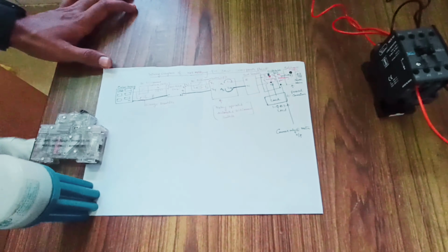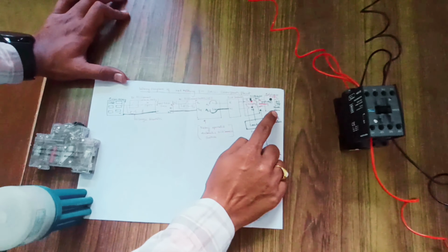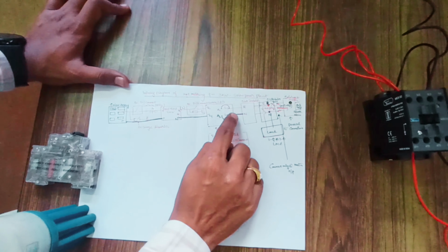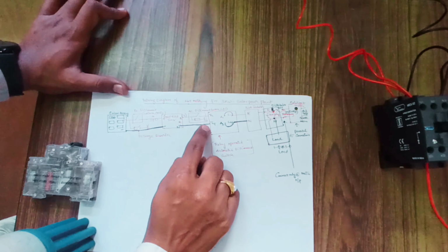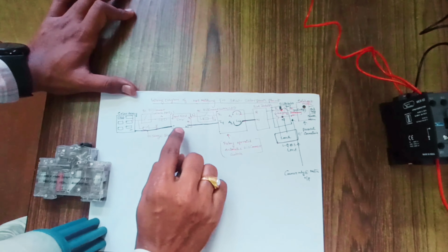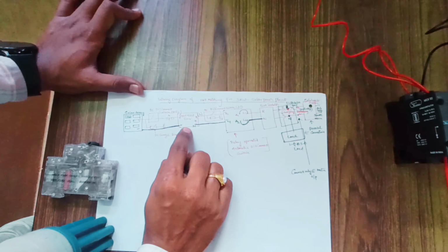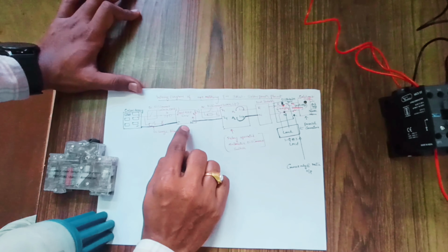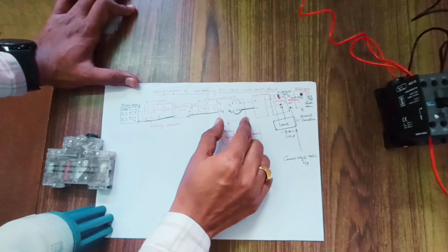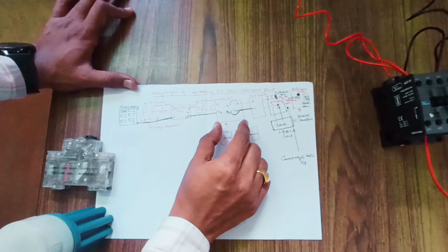Okay, so here you can see this is the meter output. The meter output we have to connect to the contactor input, and the output of the contactor we have to connect to the inverter. The purpose of the contactor is already served in this grid connected inverter, where it operates in anti-islanding mode. But the department is asking for one more contactor which prevents the entering of current whenever the grid fails. So here you can see the working of the contactor.